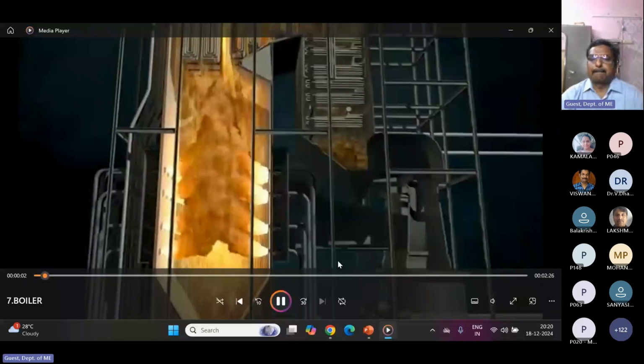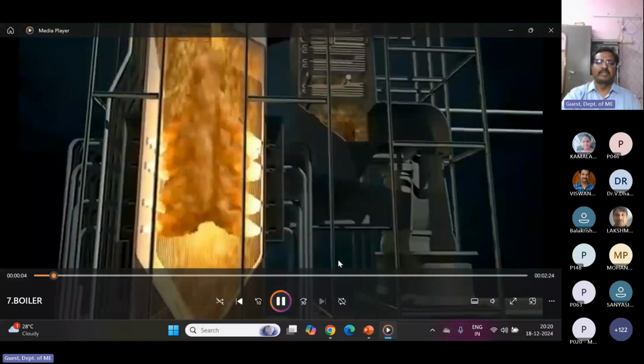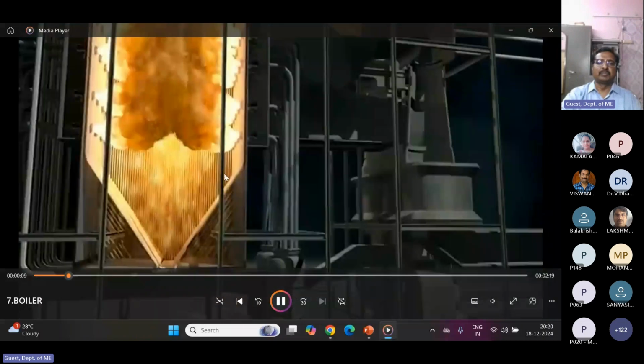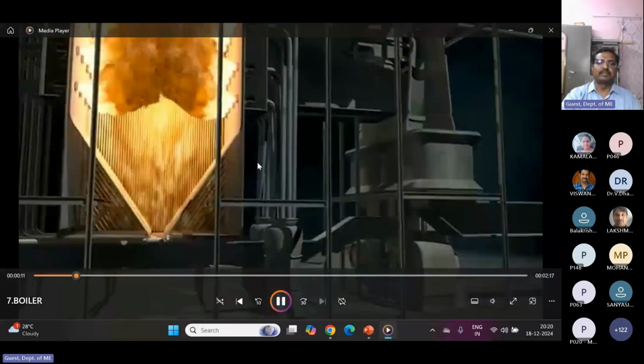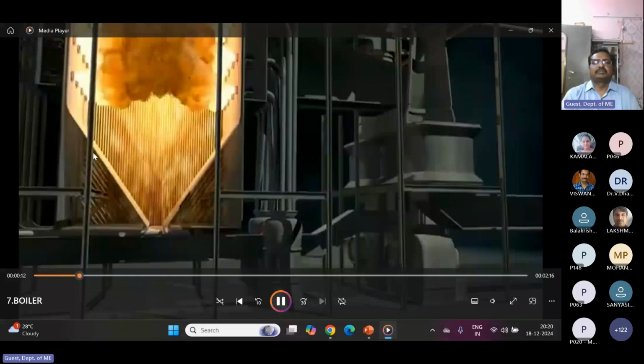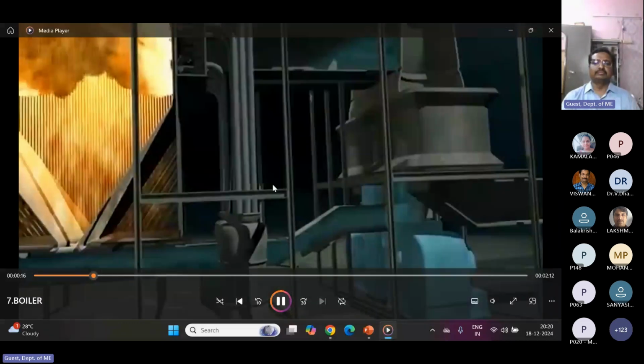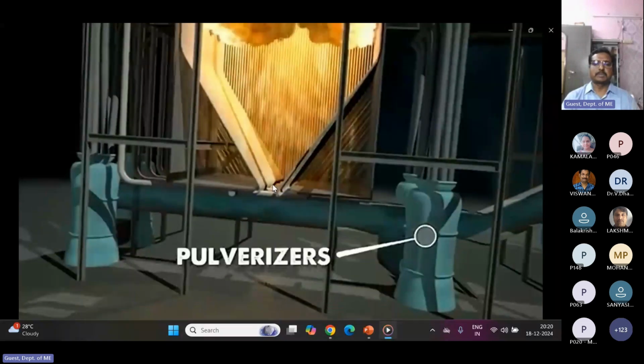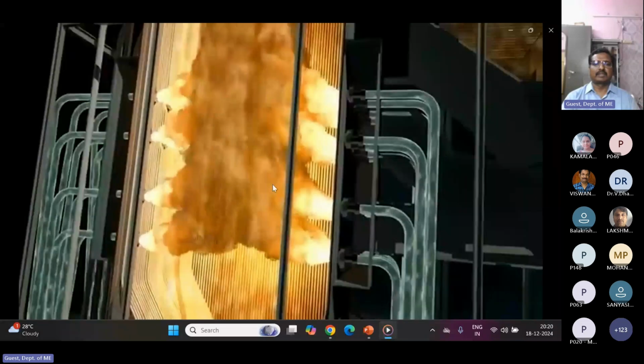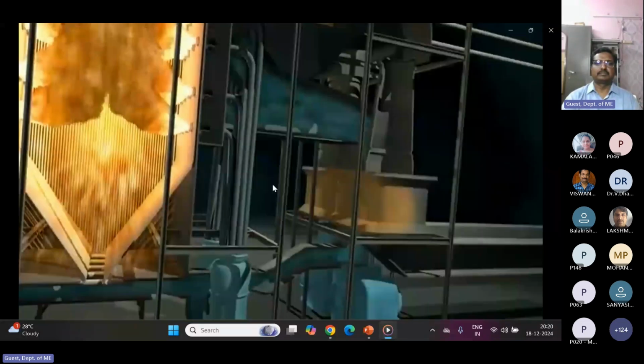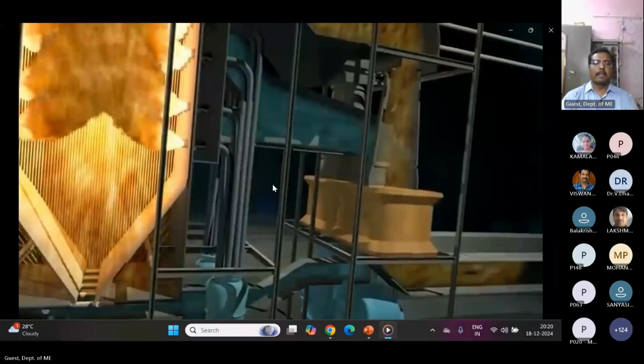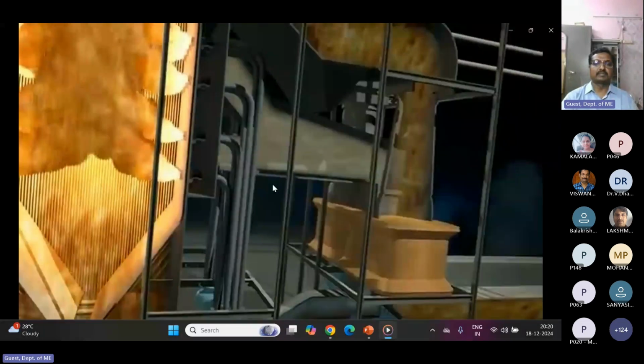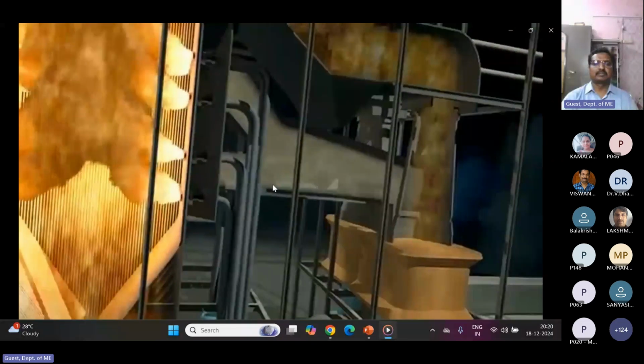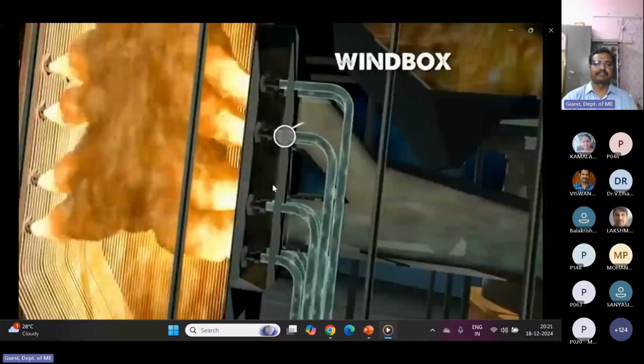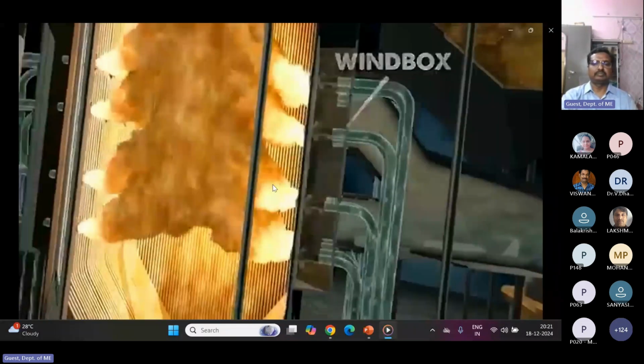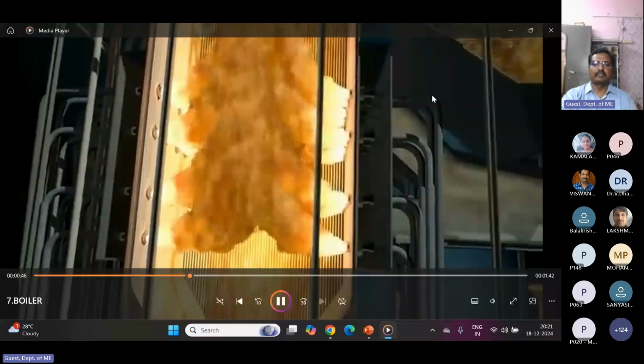Today's boilers, as they have been since their origin, involve the complex production and manipulation of steam. These are all water tube boilers. The forced draft fan blows air into the system. A portion is routed to the pulverizers, which crush coal into a fine dust before pushing the mixture up through feeder tubes. The other portion passes through an air preheater, which transfers heat from the exhaust gases to the incoming air, raising the air temperature, reducing moisture, and producing a cleaner burn. The hot forced air and coal dust converge in the windbox, where the mixture is blown out through burners and ignited inside the firebox, transferring radiant heat to the water-filled tubes.